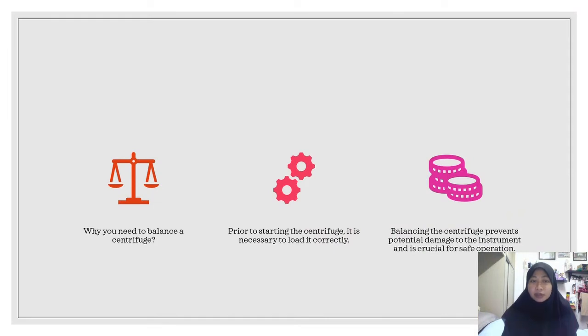Why do you need to balance a centrifuge? Prior to starting the centrifuge, it is necessary to load it correctly. Balancing the centrifuge prevents potential damage to the instrument and is crucial for safe operation.